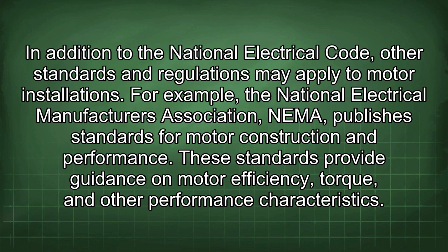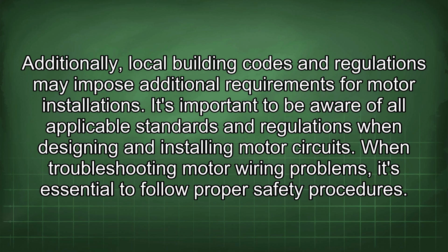In addition to the National Electrical Code, other standards and regulations may apply to motor installations. For example, the National Electrical Manufacturers Association (NEMA) publishes standards for motor construction and performance. These standards provide guidance on motor efficiency, torque, and other performance characteristics. Additionally, local building codes and regulations may impose additional requirements for motor installations. It's important to be aware of all applicable standards and regulations when designing and installing motor circuits.